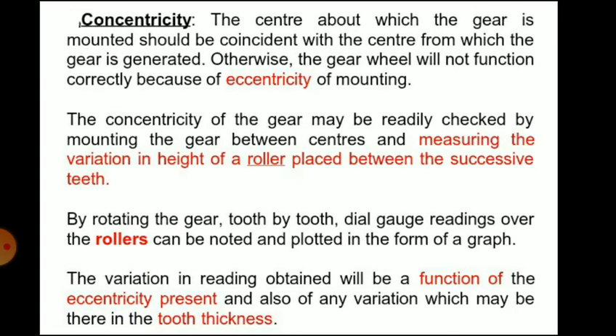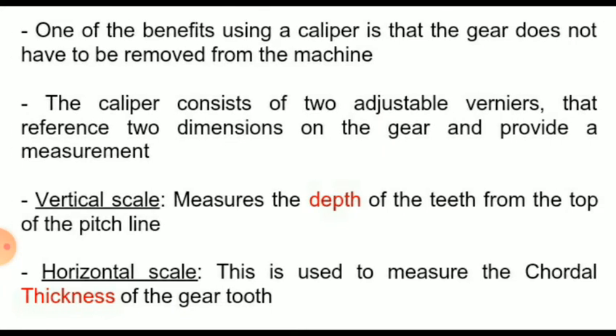This method is not very satisfactory for the following reasons: first, the vernier itself is not reliable to closer than 0.05 mm, or perhaps 0.025 mm with practice; second, measurements depend on two vernier readings, each of which is a function of the other; and third, measurements are made with the edge of the measuring jaw, not its face, which does not lend itself to accurate measurement.